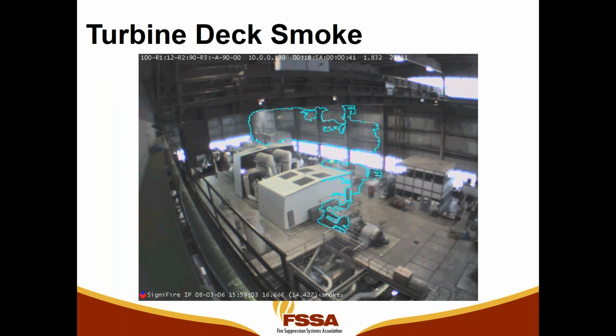So, a typical turbine deck application: you can see some oil was burned off on a lower level. The smoke migrated into the space. In this case, there are two cameras, one camera looking at this side of the turbine, and then a camera down the wall looking at the other side.